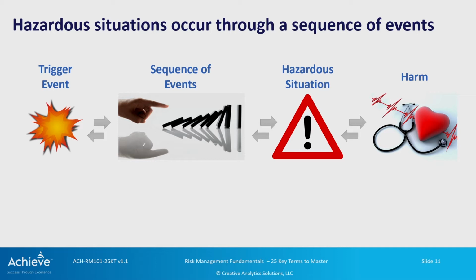And when you do hazard analysis, which we will discuss in the next module, you can do this exercise iteratively back and forth, working with your engineering SMEs and medical experts to develop a very good description of all the hazards, how they are involved in hazardous situations, and how they are linked to harms. Now, hazards are present in a hazardous situation, and it is necessary for a user or a patient to be exposed to hazards in a hazardous situation for harm to occur.